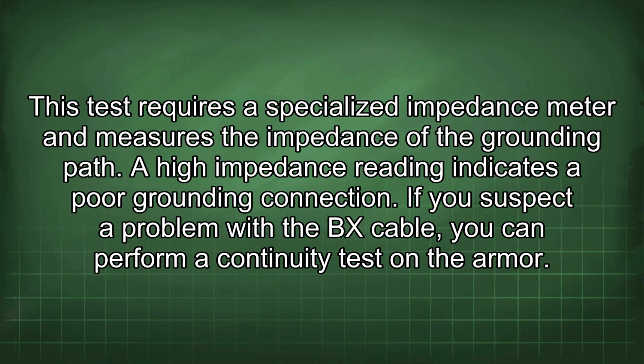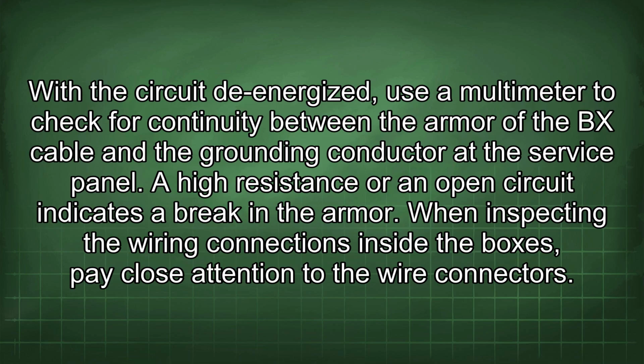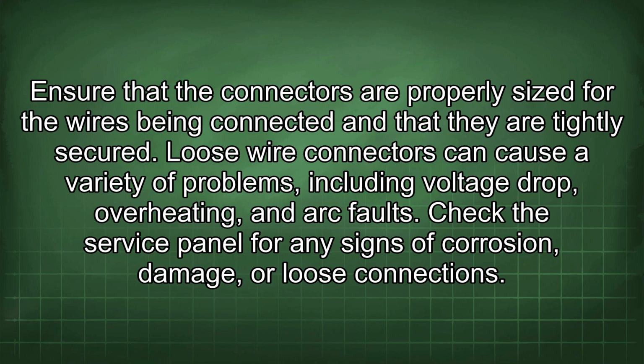If you suspect a problem with the BX cable, you can perform a continuity test on the armor. With the circuit de-energized, use a multimeter to check for continuity between the armor of the BX cable and the grounding conductor at the service panel. A high resistance or an open circuit indicates a break in the armor. When inspecting the wiring connections inside the boxes, pay close attention to the wire connectors. Ensure that the connectors are properly sized for the wires being connected and that they are tightly secured. Loose wire connectors can cause a variety of problems, including voltage drop, overheating, and arc faults.